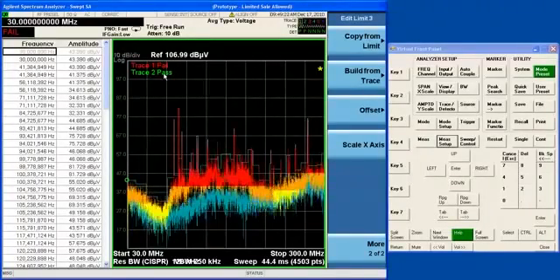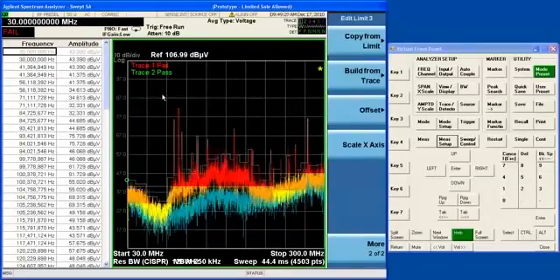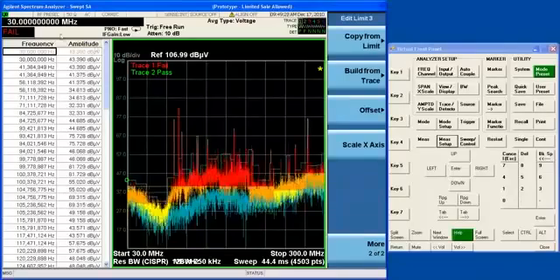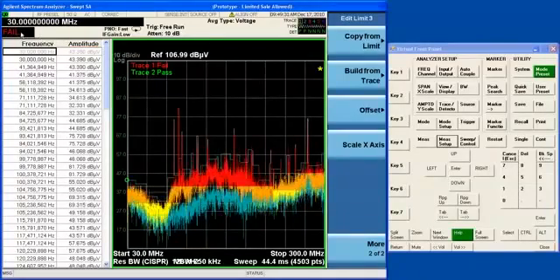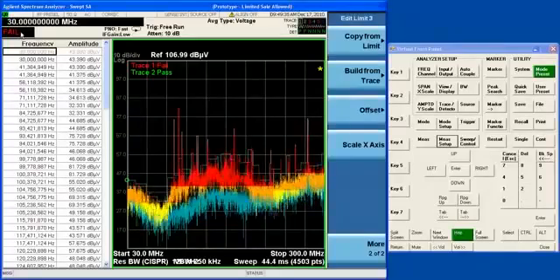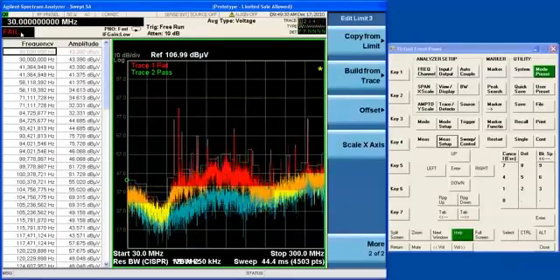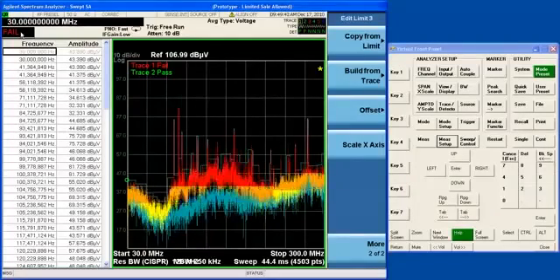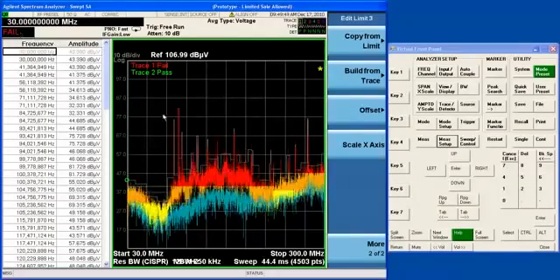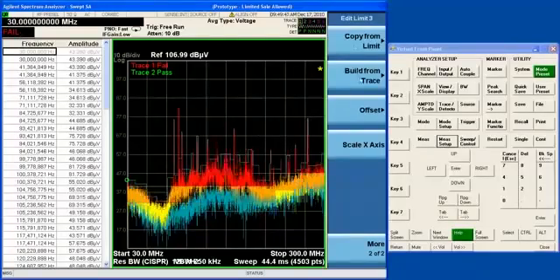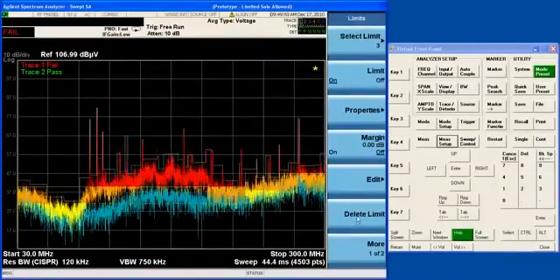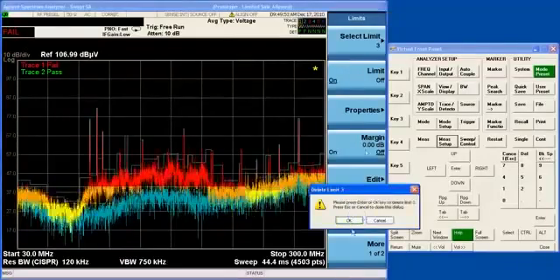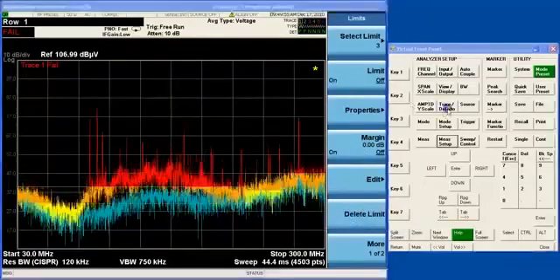And you can see that it is reporting the limit results for both Trace 1 and Trace 2. It will report limits for each of the six traces here in the corner of the display. And then the summary area here shows you if any of the existing limits is causing a failure to any of the traces. So a lot of capability built into the limit system and the limit editor. I am going to turn off Trace 2 and I am going to delete limit 3 because the display is getting a little busy here.